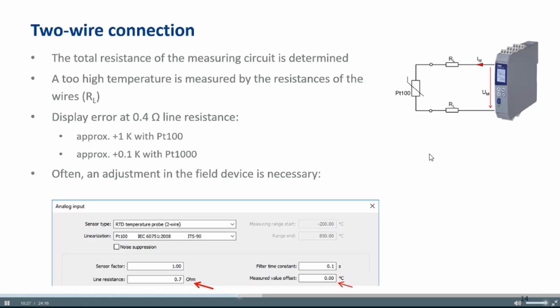So how can you manage this? How can you have the right temperature? You need to make an offset. You need to say, okay, the offset which comes from the line resistance, I need to compensate. And if you work with our devices, then in most cases you have the possibility of defining the line resistance directly. Maybe it's possible because you have a terminal, something like this, and you can measure the ohmic resistance. Maybe it's 0.7 ohms. Then you enter it directly, and then you have made the offset correction which comes from the cable.